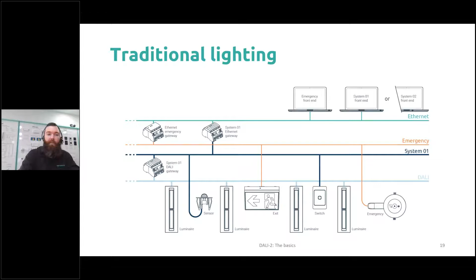The actual communication between two systems, I like to consider it like a Venn diagram. You've got everything system A supports over here, and everything system B supports over here, and what you can achieve from your total system is only the overlap between the two. So if something is supported in the DALI space but not in the BMS space, even if you've installed new devices and updated your controllers to support the latest protocols, you're not going to be able to do anything with that information until the other system supports it as well. Whereas if you have one system looking after the input devices, emergencies, and lights, as these updates become available, it's very simple to increase the capabilities of your system.